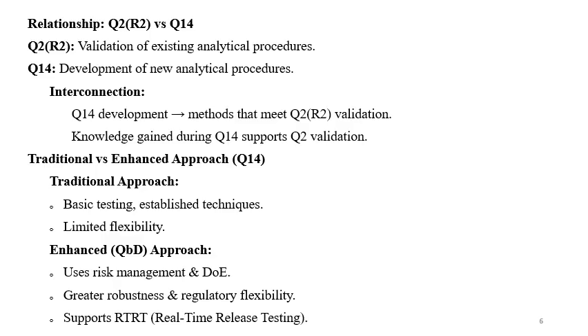Coming to the relationship between Q2 and Q14: Q2 is for validation and Q14 is for development. ICH Q2 is for validating existing analytical procedures, while Q14 is for developing new analytical procedures. There is an interconnection — Q14 development produces methods that meet Q2 validation requirements, and knowledge gained during Q14 development supports Q2 validation.